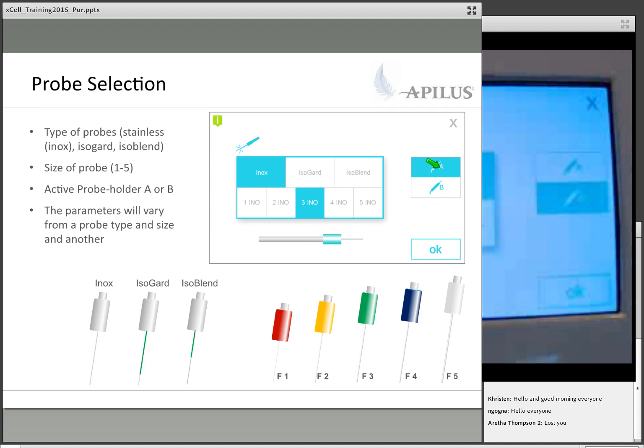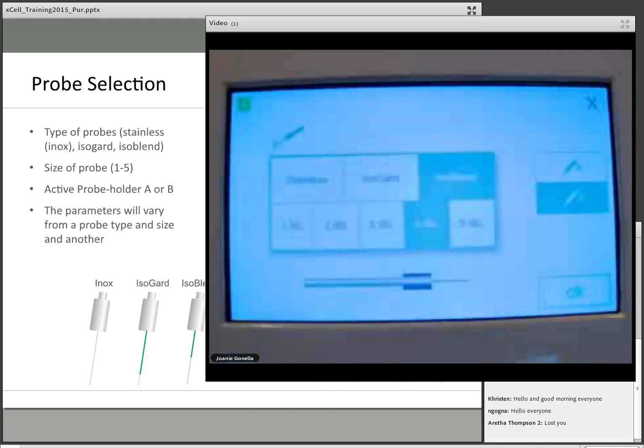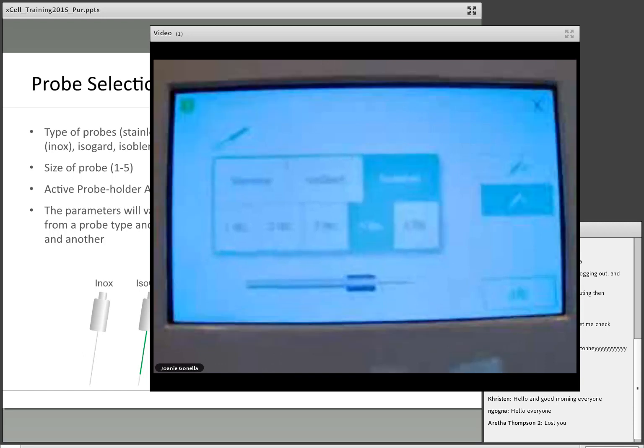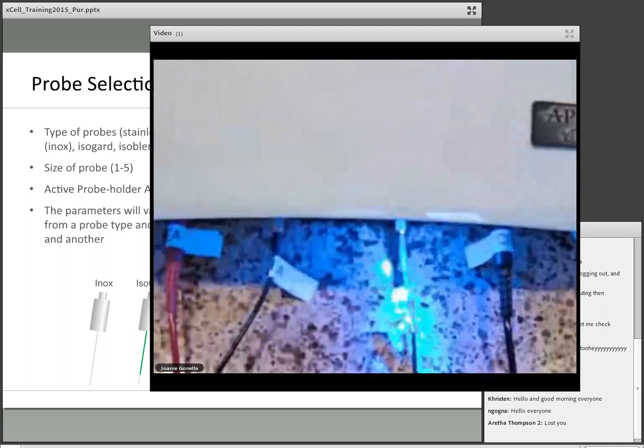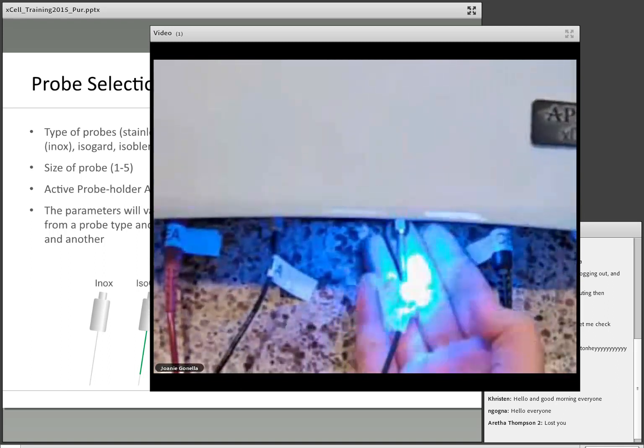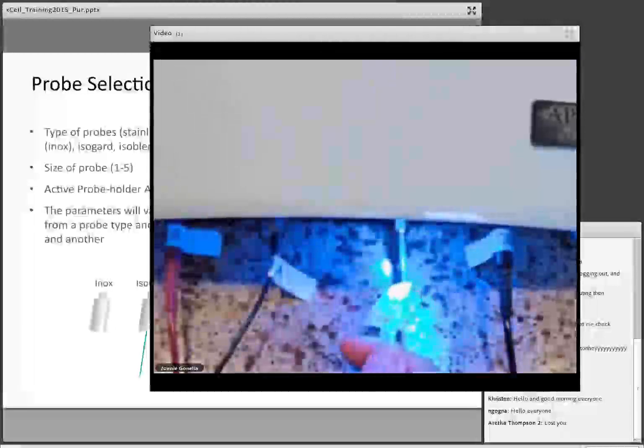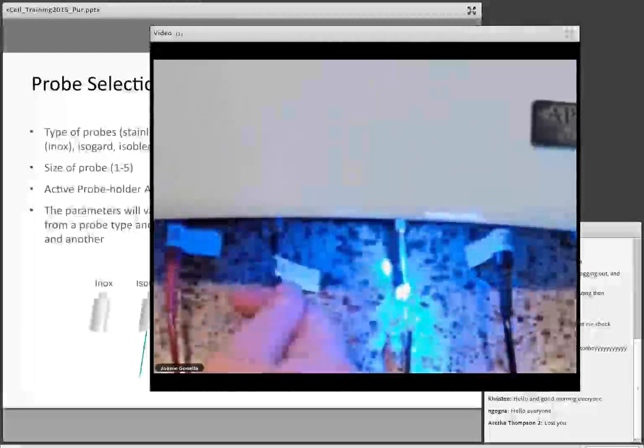Another very important thing on the screen is which probe cord you are using. We have A and we have B. How you know which cord is active is the one where the light is lit up on top of the probe cord. So when we go back to the video, I will show you that down below. I have my 4 cords plugged into the machine, and there's one that's lit up, which is this one here. So that is the probe cord that is active right now. If I were to use this one to do my treatment, no current would come out at all.